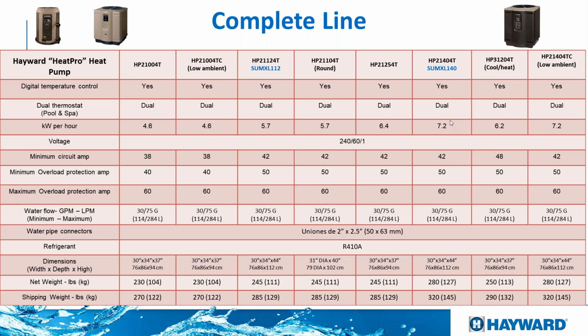And then that is going to give us the consumption per day or per month, however we want to see it. Also keep in mind that all of our heat pumps require a maximum breaker size of 60 amps, and the flow that it requires is 30 to 75 gallons per minute. So keep in mind, if we're installing this with a bigger size pump, let it be 2, 2.5, 3 horse, all of those require an external bypass.